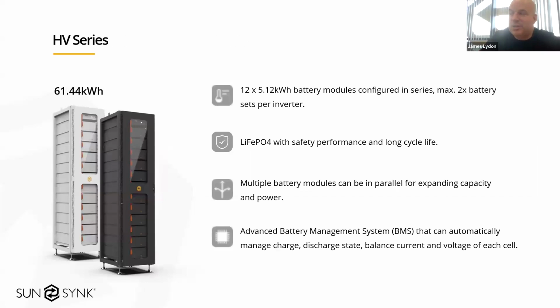Okay, so the HV batteries, so you can see here, these two stacks. Each module in there is a 5.12 kilowatt hour low voltage battery. But typically with the low voltage batteries, if you were connecting multiple together, you would connect them in parallel. These are all connected in series. So once it gets to the top, we're at sort of 600 volts plus. So yeah, each stack is 61.4 kilowatt hours of storage. It says at the top here, max two battery sets per inverter.